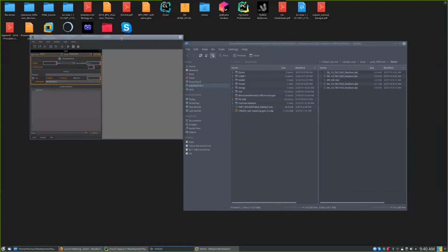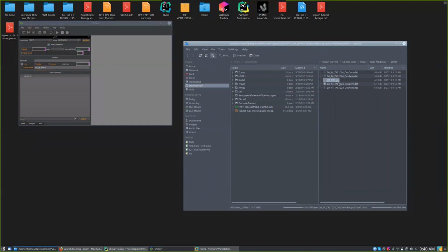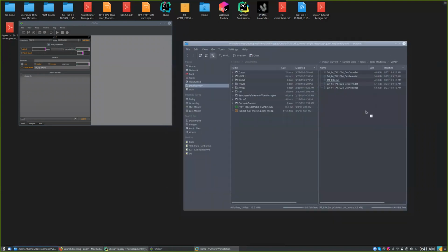So the easiest now is if we start with the donor only. First of all, to analyze the data, we need the instrument response function of the donor channel. And you can load the data just by clicking on this file and dragging it here to this data set, the lower data set window. First of all, you have to check what file format that is. If I open the file, this is a Claus Seidel lab specific file format where parallel and perpendicular detection channels are just saved subsequently in the file, without an additional column which specifies the time. What is shown here is just the counts detected in the histogram.